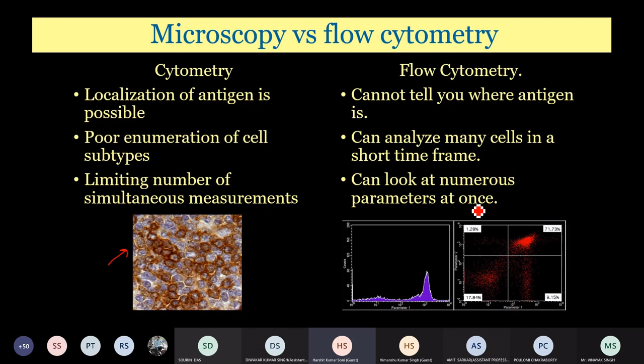So what happens in a flow cytometer? In a flow cytometer, cells are present in a suspension and they flow in a single file path. What that means is that at a time only one cell passes the laser. It should not happen that instead of 1, 2 are passing. If 2 pass, then whatever data you are getting is for the 2 cells, so it will be wrong. So you have to have a cell suspension in which all the cells are single cells, not clumps of 2 or 3 cells together. This comes under the part of fluidics.